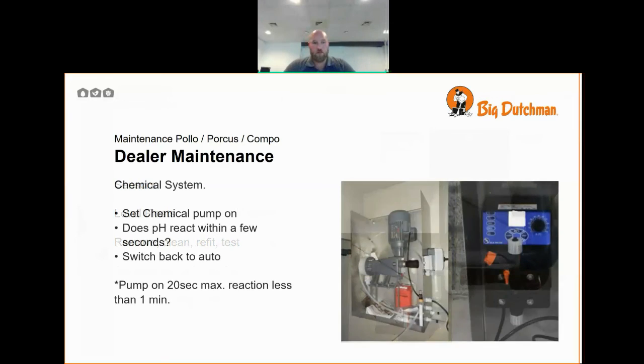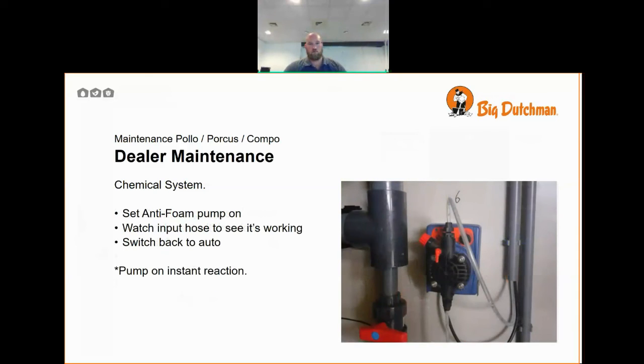And the chemical system. Set the chemical pump on and watch for a reaction within a few seconds on the pH level. Then switch back to automatic. Put the pump on for 20 seconds max. You should see a reaction in less than 1 minute. Check the anti-foam pump, set it on, and watch the hose to see that it's working. Then set back to automatic. The pump's reaction should be instantaneous.